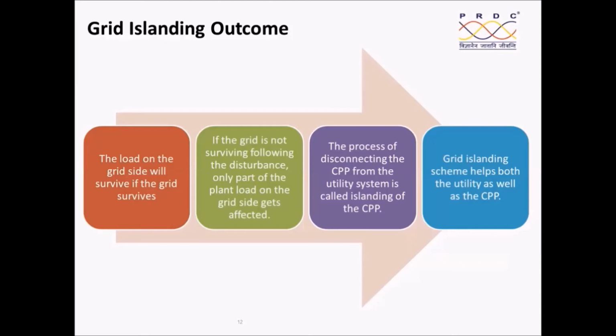The outcome of the grid islanding is therefore that the load on the grid side will survive if the grid survives. What it means is, we can try to ensure that the grid is there and also the captive power plant is there. Assume that the islanding breaker is in between the grid bus and the captive power plant bus. There is the essential load and the non-essential load. Then the load on the grid side will survive if the grid survives. If the grid is not surviving following the disturbance, only part of the plant load on the grid side gets affected. So on the plant side, everything will be surviving. On the captive power plant side, whatever loads are there, they will be surviving.